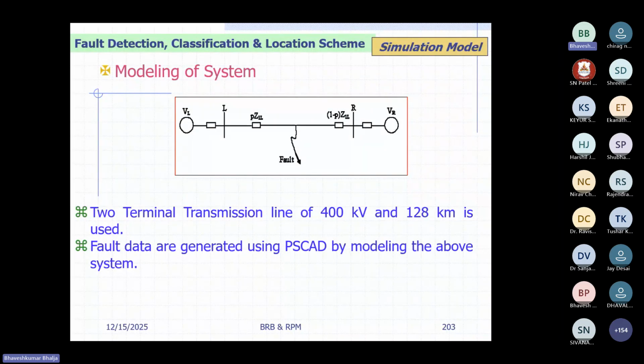Then you have to consider the fault inception angle. At what angle does the fault occur? Now, what is fault inception angle? So we know that whenever a fault occurs, on the left hand side I have shown one source VL. If you draw the equivalent circuit of this, there is an AC source, let's say E equal to Em sin(omega t plus phi). And then there is a transmission line with parameters. Let's say you consider lumped parameter or medium line, or distributed parameters for a long transmission line, nominal pi model, nominal T model, depends. So line parameters are there, R, L and C.